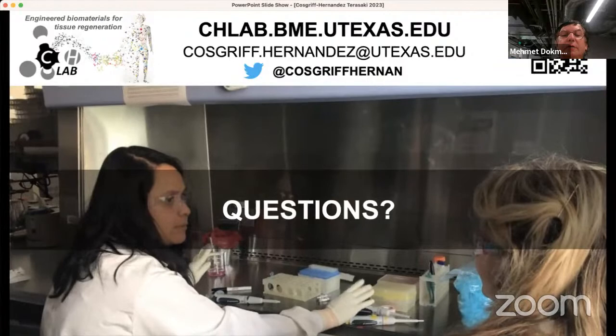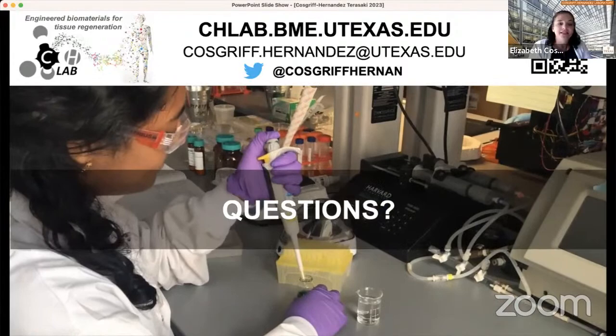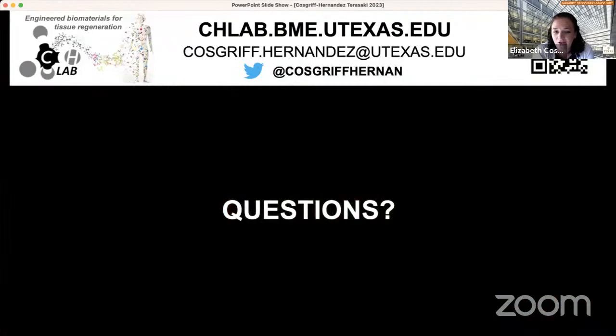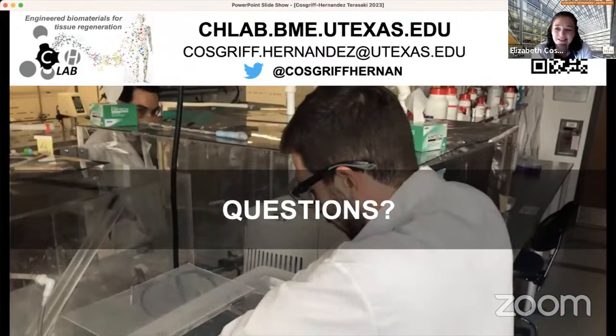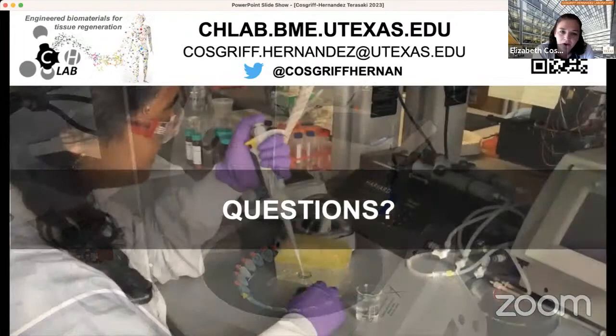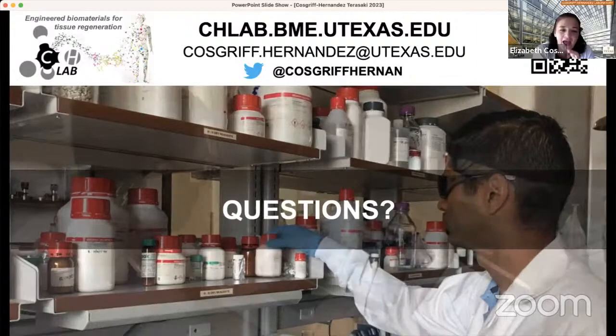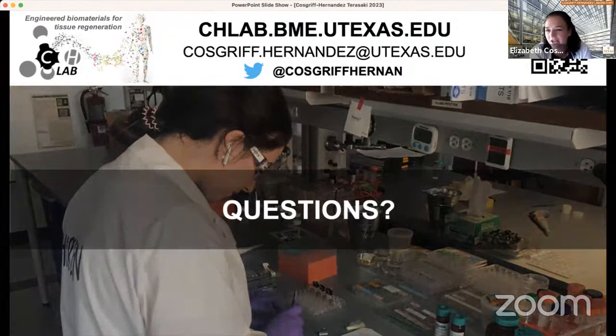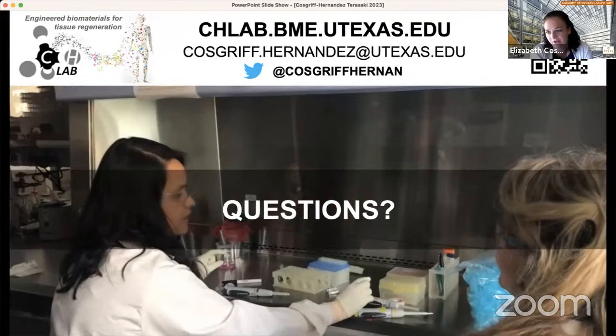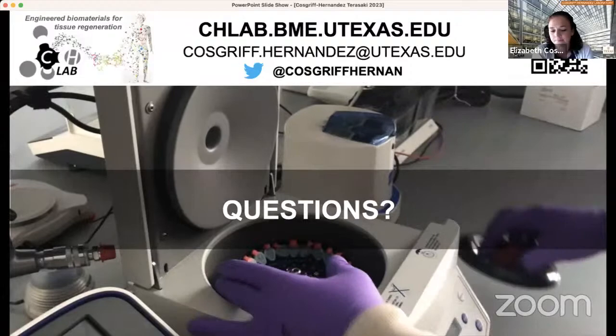What is the degradation rate of the hydrogel? How long will it stay at the site? Our initial studies did accelerated degradation testing taken out to six months. If I was going to predict the acceleration factor to in vivo, I would say it's at least tenfold, and so we're looking at that being a prediction of at least five years with no change. That being said, we would need to do additional testing and confirm that. We have had some issues with synthetic batch variability that we're trying to chase down currently. But from a structural perspective, the base chemistry — as long as we get consistency in that structure — will be very stable long-term, so we're talking about decades.